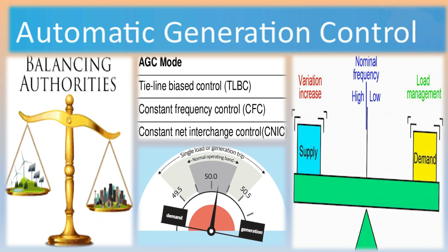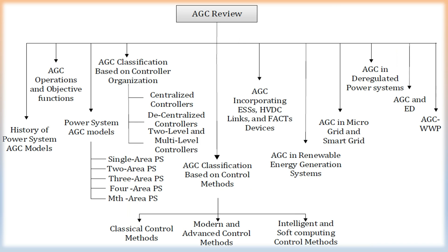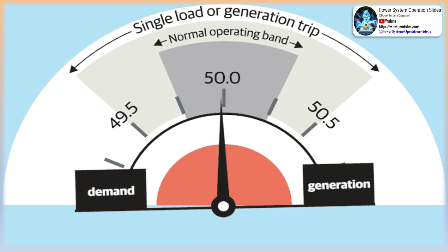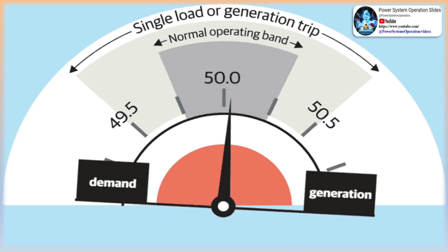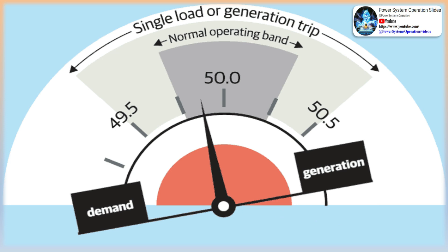This AGC course will provide an overview on how generation in a large high-voltage system is automatically controlled. Included is a description of the different modes of control and the parameters of the control settings, also the instructions in detail required for the generation dispatcher to become proficient in the operation of Automatic Generation Control AGC. AGC is a computerized system located in the control centers on the generation dispatcher's desk. This program will automatically balance generation and load providing it is used within defined limits.